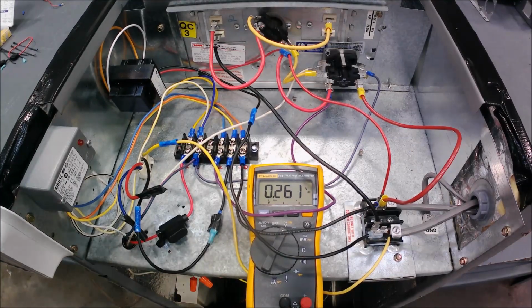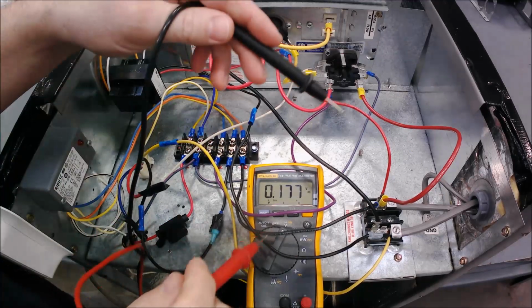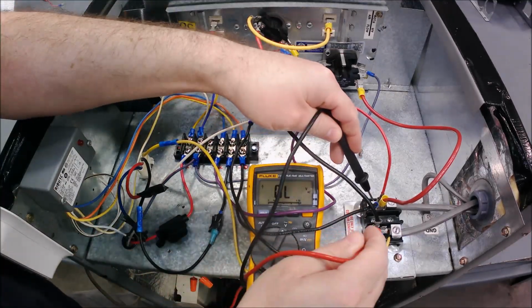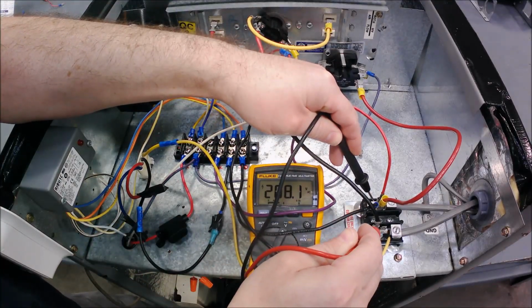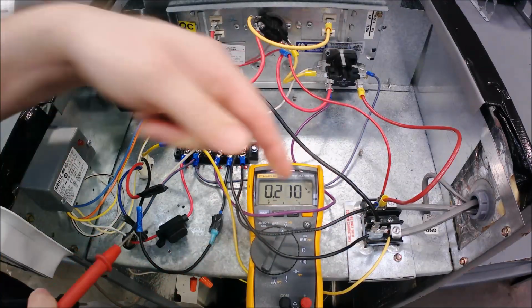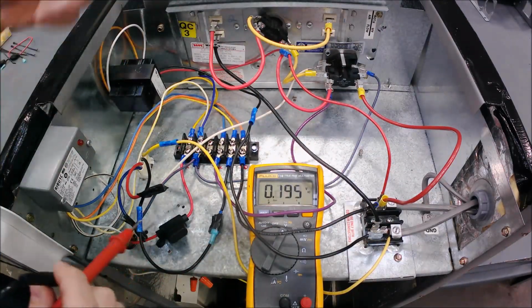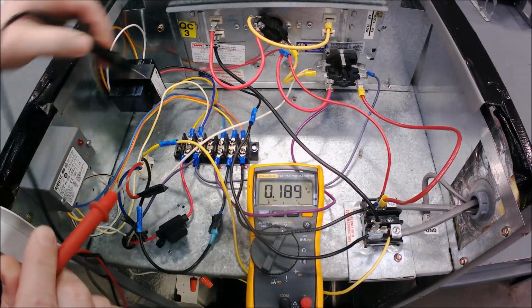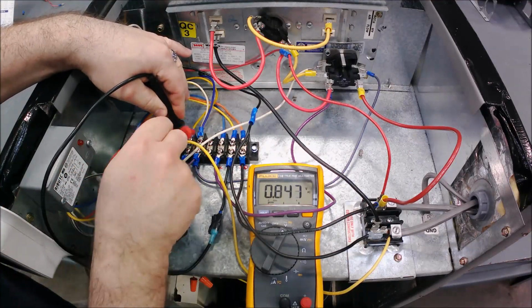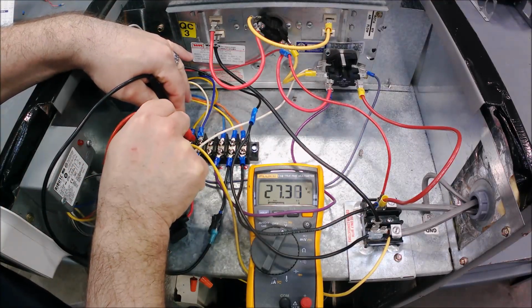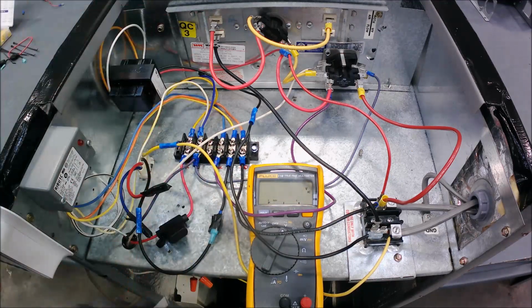Alright, so we can do a couple things. With the power off, of course, our terminal block is over here, and you can see we're pulling about 208 volts. That power is going to go to the transformer. If I was going to check 24 volts out of the transformer, then I'm going to check over here on the low voltage side of this terminal strip. We got 27 volts going.